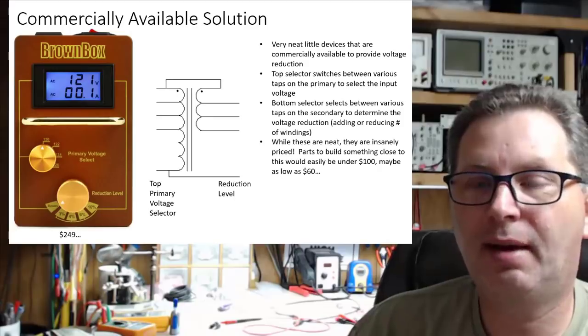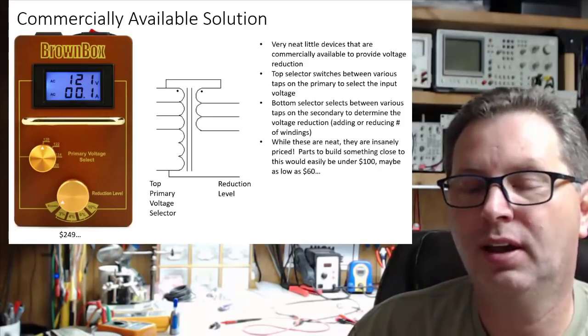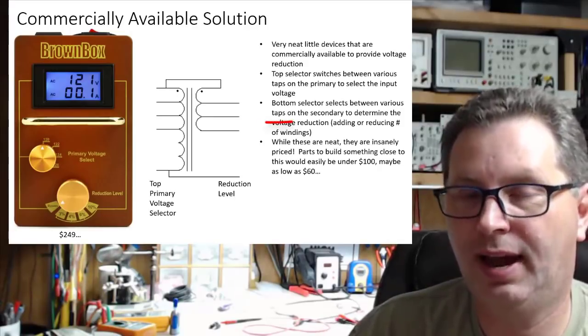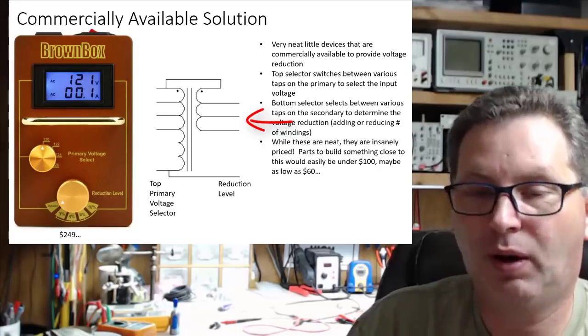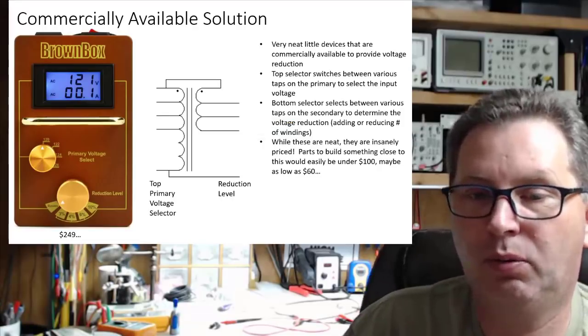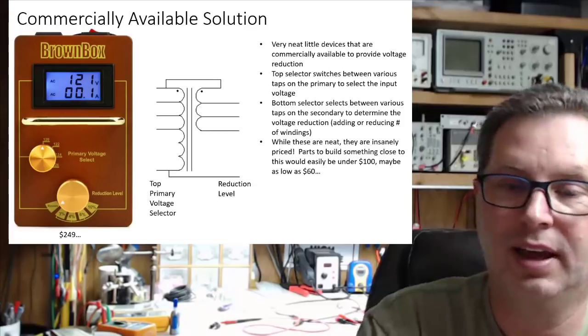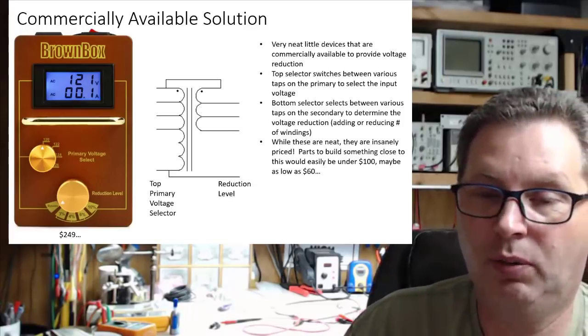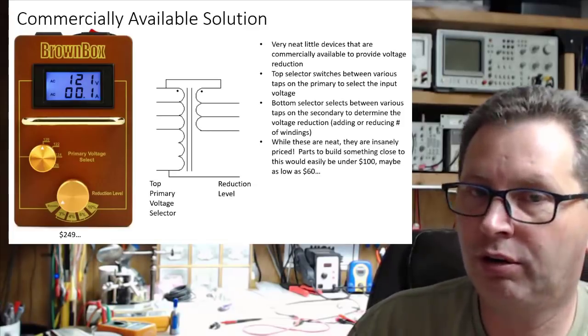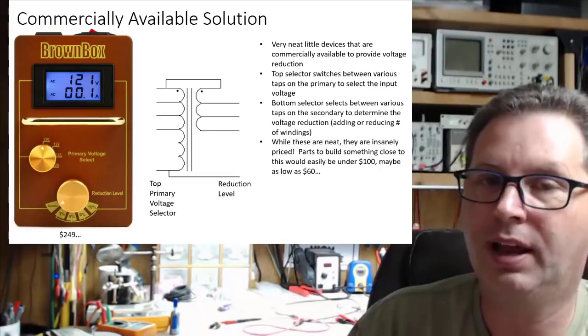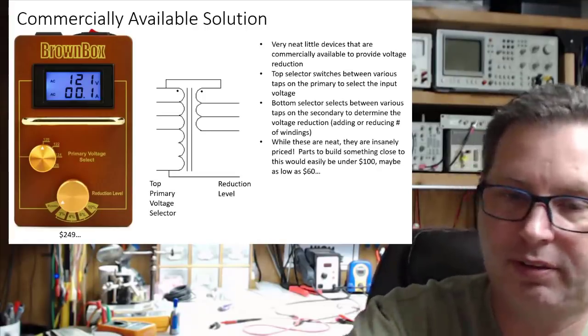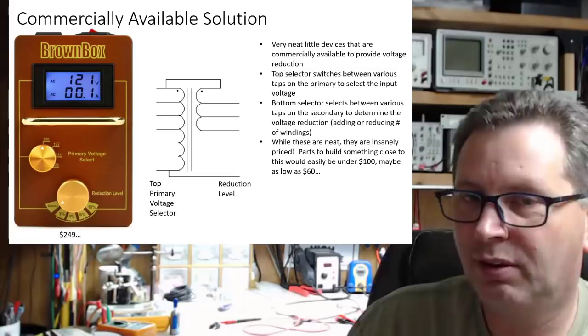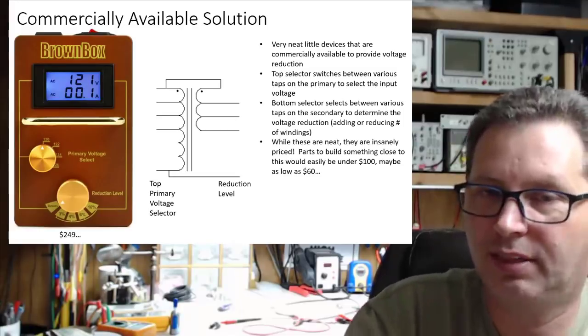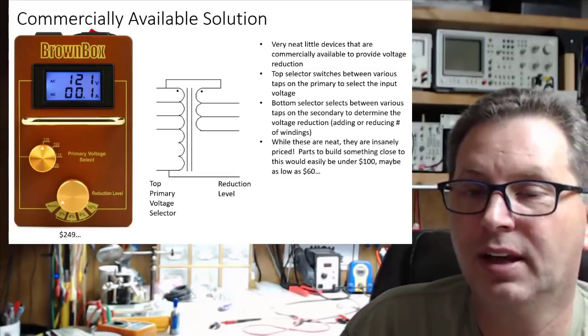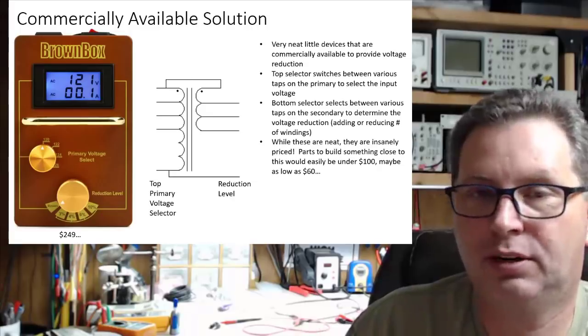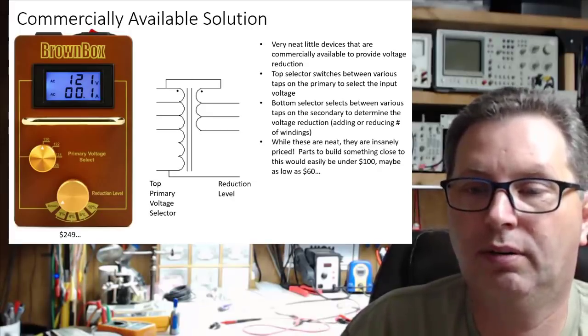They achieve that because the transformer they use has multiple taps on the output, but it's wired exactly the way I showed a minute ago. You essentially have these secondary windings, and depending on which tap, that determines how many turns are in series with the primary, out of phase. If you flip this over, even though the dots look like they're in phase, when flipped to the other side they're actually out of phase. Based on the tap selected, that determines the number of turns and thus the amount of reduction.